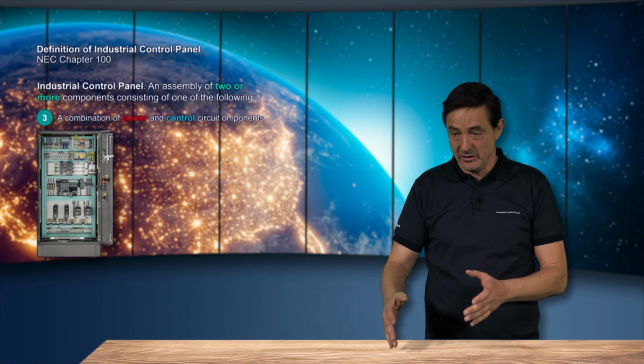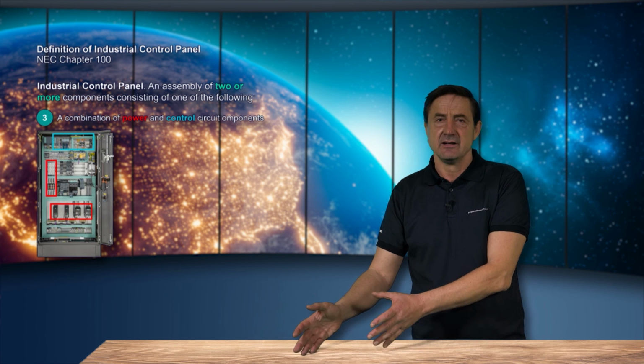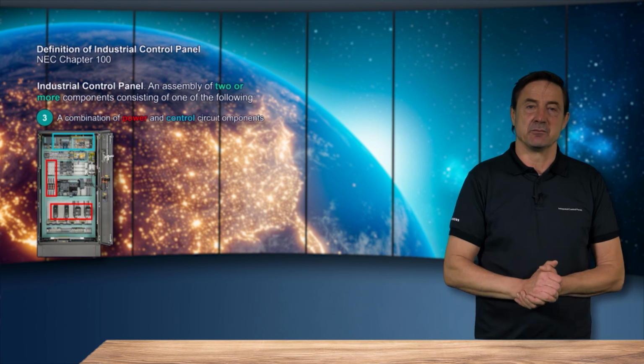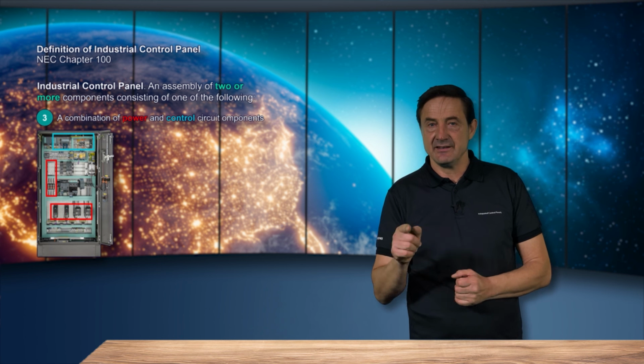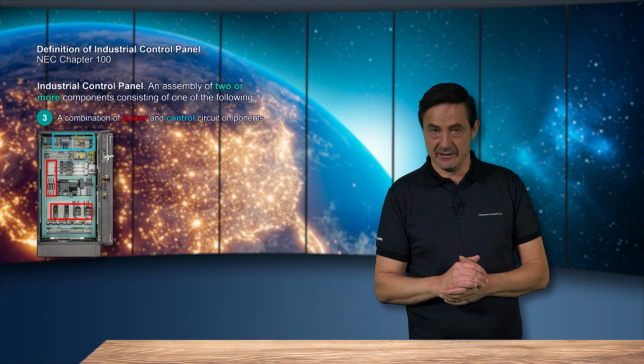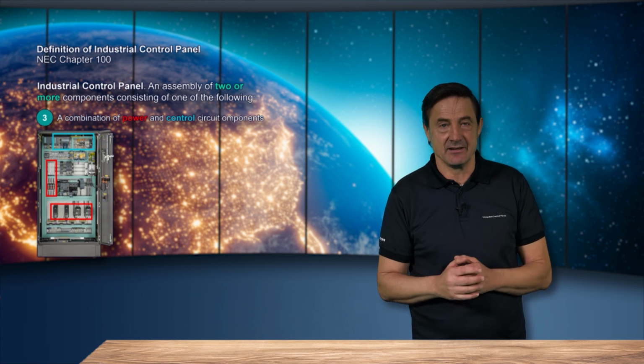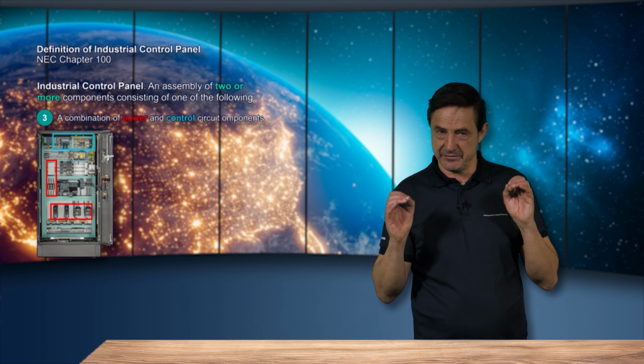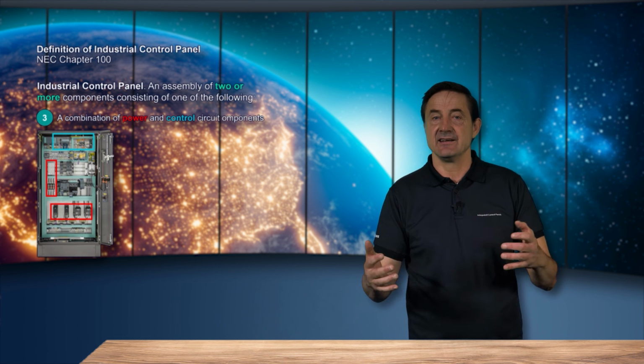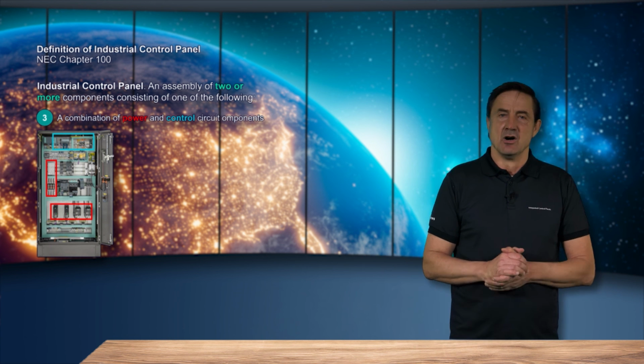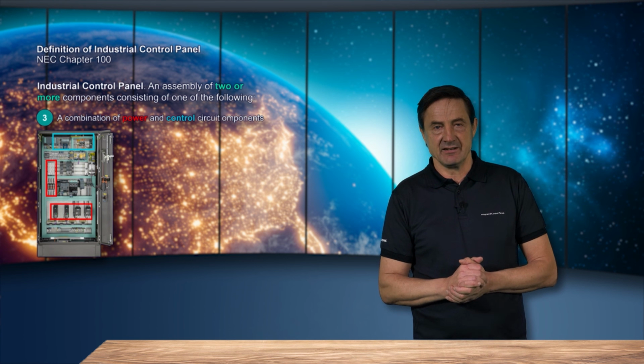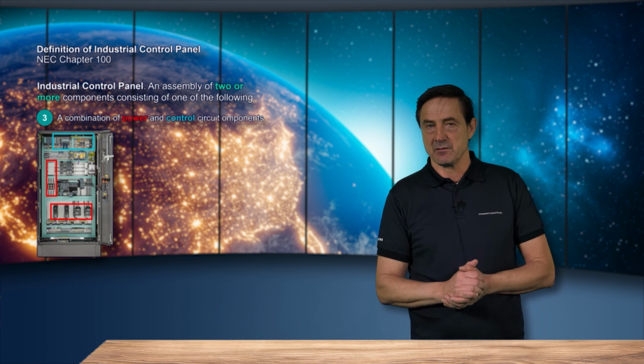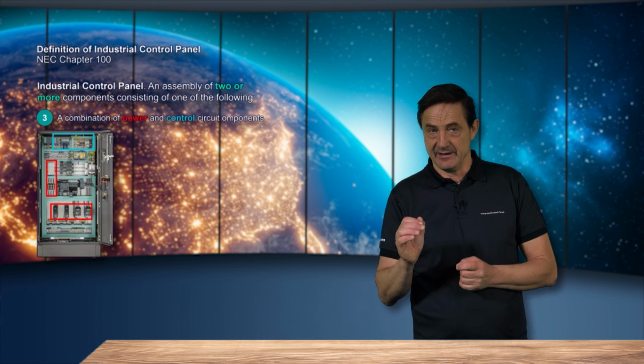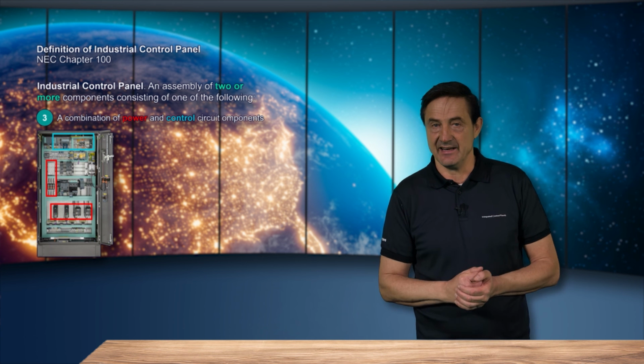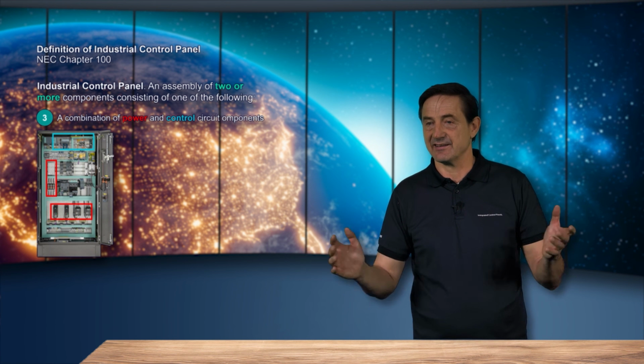Last but not least, a combination of a power circuit component together with a control circuit component inside an enclosure, independent of voltage or power, is by definition already an industrial control panel. The applicable standards for these are UL 508A in the USA and CSA number 286 in Canada.